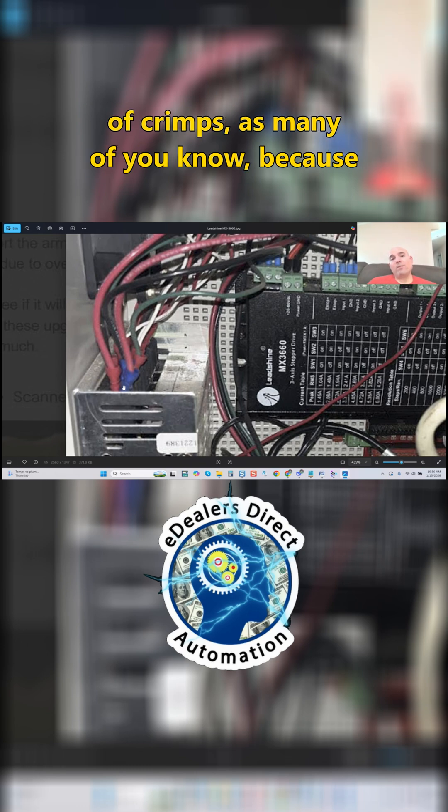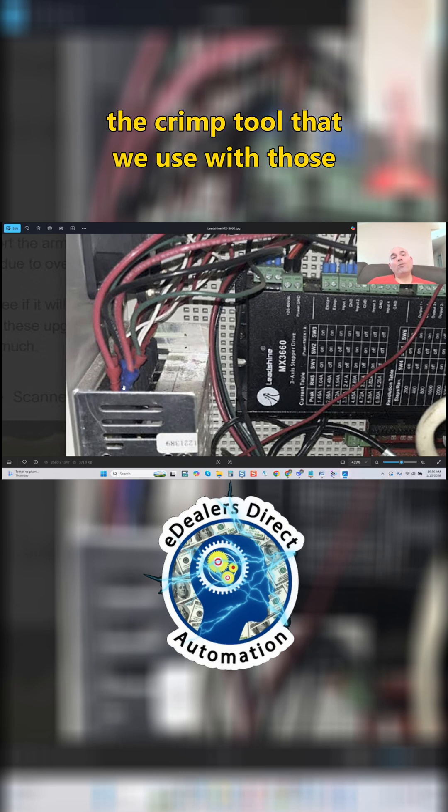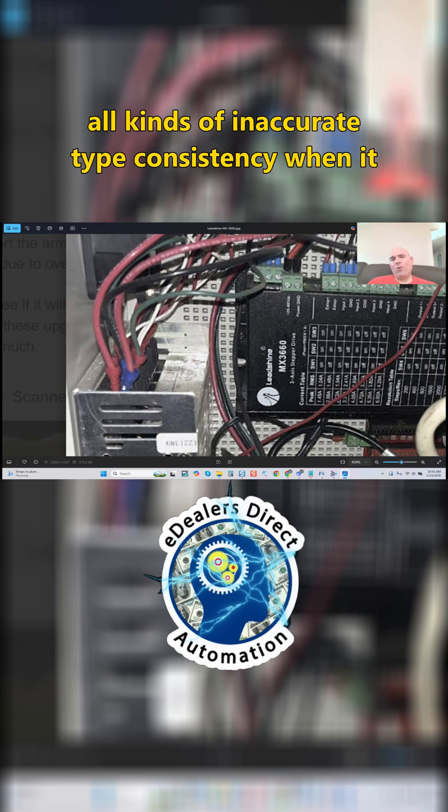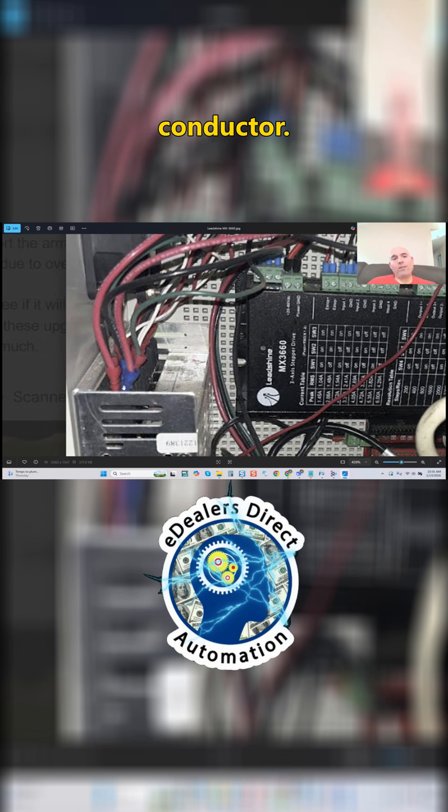I'm not a big fan of crimps, as many of you know, because crimps unfortunately are not a precision tool. The crimp tool that we use with those crimps can fracture conductors and create all kinds of inaccurate-type consistency when it comes to creating a nice bond to your conductor.